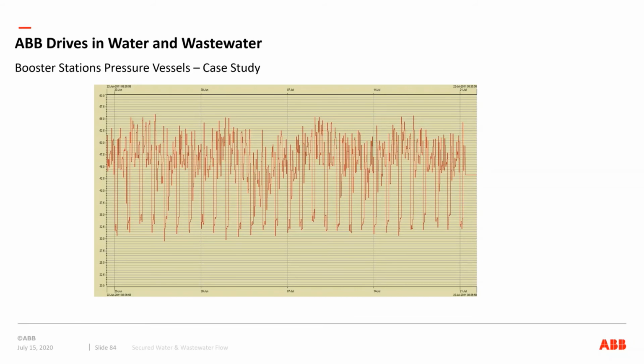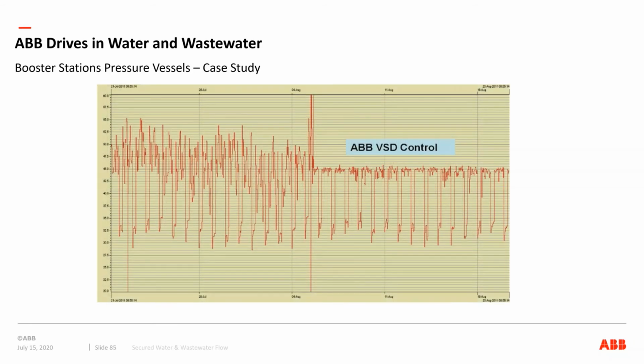I wanted to show this graph here because I wanted to show the pressure vessel. This is when we're using on-off control for a water tower, and you can see there are very significant spikes. We've not really talked about constant pressure applications here, but one of the advantages of constant pressure, if we can go to the next slide, is being able to control these wide swings that we see on these graphs. And you can see here, we go from the wide swings and we put a drive in there, and we have two types of pumps in here. We have a larger pump and a smaller pump, and we're oscillating between the two.